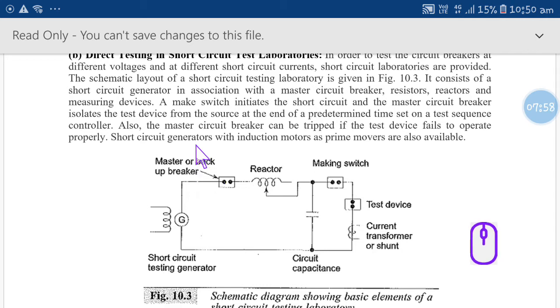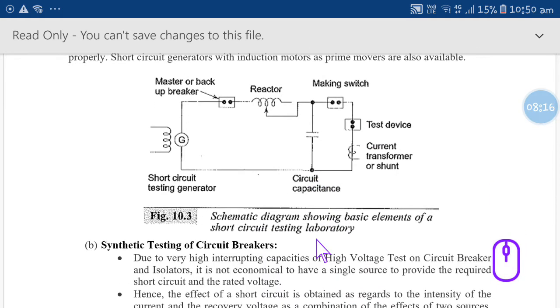Also the master circuit breaker can trip if the test device fails to operate. So this will trip, like a backup. And a short circuit generator with an induction motor as a prime mover is also available within this, okay. And this is the current transformer, this is the test object and capacitive circuits. This is the schematic diagram of what they do under the short circuit test.